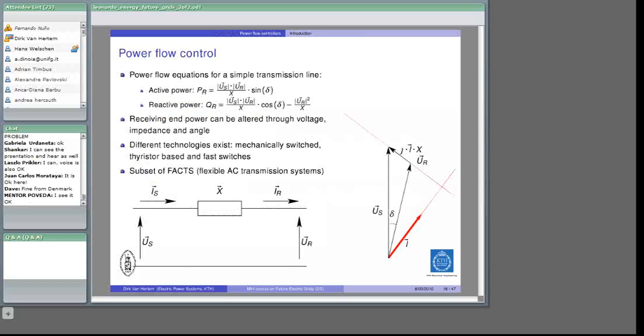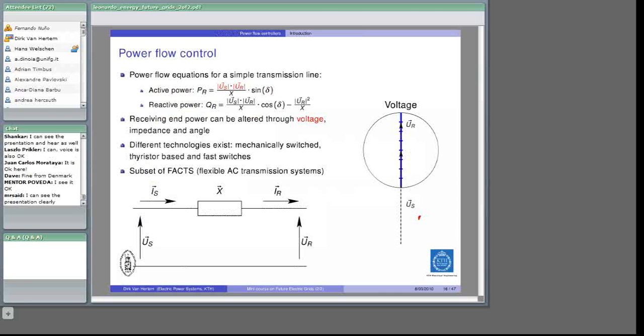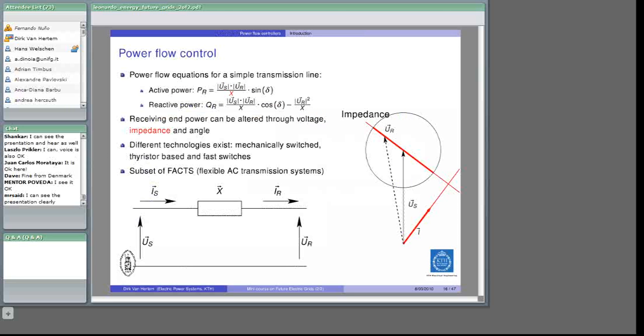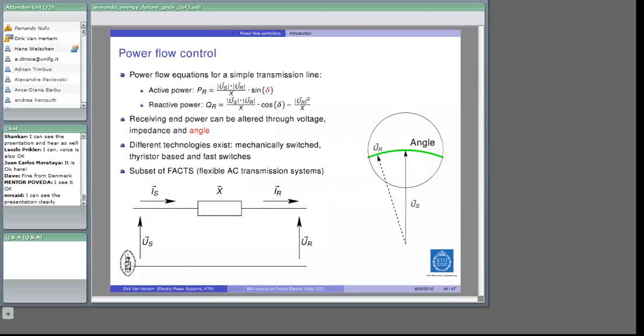So what can we do with our power flow equation? As you can see, we can change the voltage at the end sides, though only with limited possibilities, since voltage still needs to stay within plus or minus 5 or maybe 10 percent. The second thing we can play with is the impedance of the line. The impedance itself can't be changed directly, but you can alter the total impedance by adding a reactor or a capacitor. Lastly, we can change the angle between the voltages at the two ends.